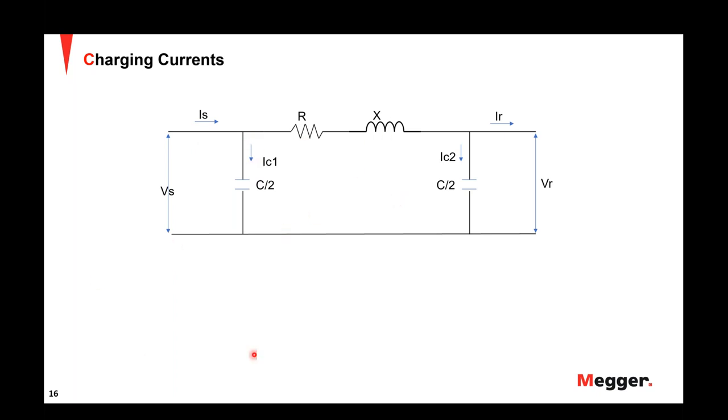And since the relays are monitoring the currents from both ends, these charging currents could appear as a differential condition to the line differential relay, and this can cause unwanted operation even though there is no fault on the line at this point in time, right?